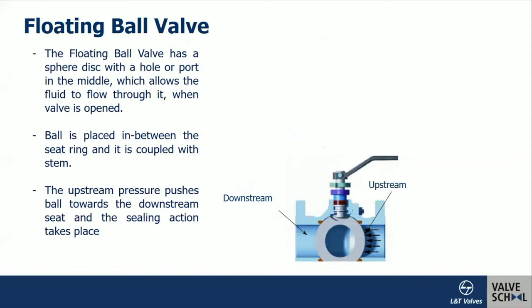As the name implies, in a floating ball valve the ball — which is the closure member or obturator — is not rigidly held on its rotational axis. It is allowed to float between the upstream and downstream seats. The upstream pressure always pushes the ball towards the downstream seat, and effective sealing takes place.